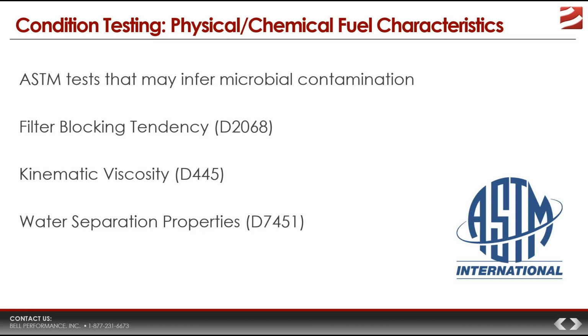And we also know that microbes consume smaller hydrocarbons in the fuel mix, which can affect the viscosity in a negative way. So if the viscosity is off, then microbial contamination might be something that you give as a possible culprit for that.